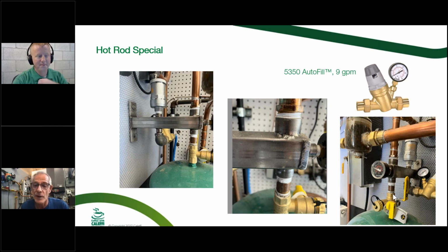And notice too on that lower right picture, that's what I call one of the Webstone valves, and that's one of them that you can purge from two directions. See the little label on it where it's got arrows both ways? If you flip that handle over, I could purge my air out of that line if that was a concern for me. Then I could turn that handle over, shut it off, and now I can purge out of the tank to drain my tank off if I want to recheck the air charge or replace it. So that's a handy valve where you can work from both directions, and it's got a nice hose connection to put a hose on it and take it to a bucket or a drain to drain it off.